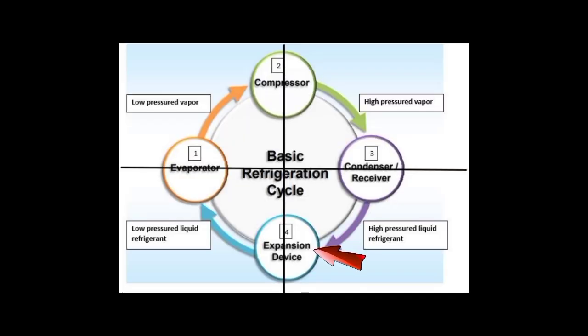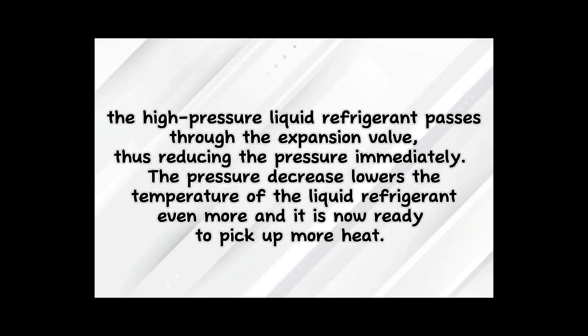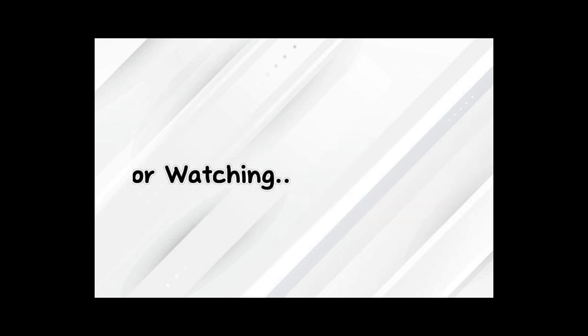At point 4, the high pressure liquid refrigerant passes through the expansion valve, thus reducing the pressure immediately. The pressure decrease lowers the temperature of the liquid refrigerant even more, and it is now ready to pick up more heat.